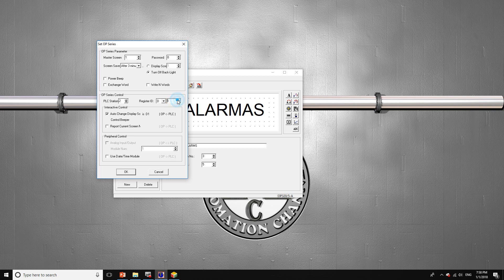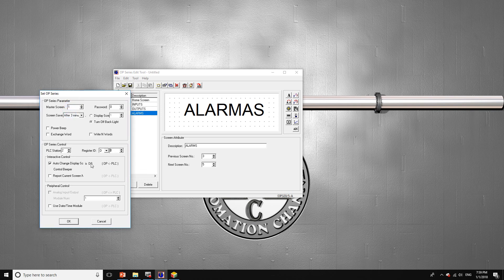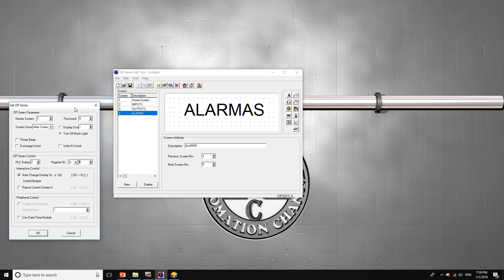You're going to use the value D0, or whichever register you want to assign — you can assign any, but right now we're going to work with D0. Depending on the value of D0, that is the screen number the operator panel is going to display. If D0 is equal to 1, the home screen is shown; equal to 2, the inputs; equal to 3, the outputs; and equal to 4, the operator panel changes to the alarms screen.